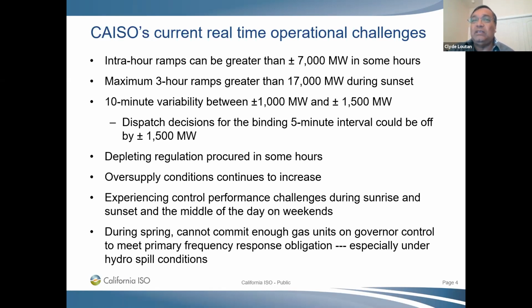So the system frequency, if something happens all the way in Colorado, we see an impact. So controlling system frequency is pretty critical. It's one of the NERC requirements. And that requirement is every minute we have an obligation as a balancing authority to support the interconnection frequency. This is why in the US, integrating renewables is a little more challenging, because we have a lot of real-time control performance standards that you must comply with. So we can talk a little more about that further down.